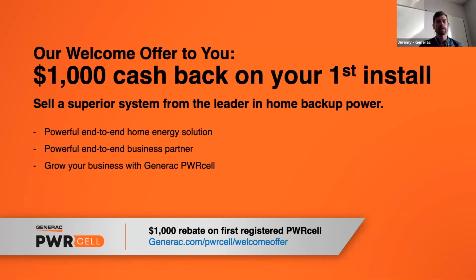So it's going to cost a couple hundred dollars more probably to install a hybrid islanding type inverter over a bare bones PV-only inverter. But I do think it will pay dividends downstream when you want to come back to that customer and add a battery—making that installation simpler and higher performance, rather than a bolt-on retrofit that might leave a few things to be desired.